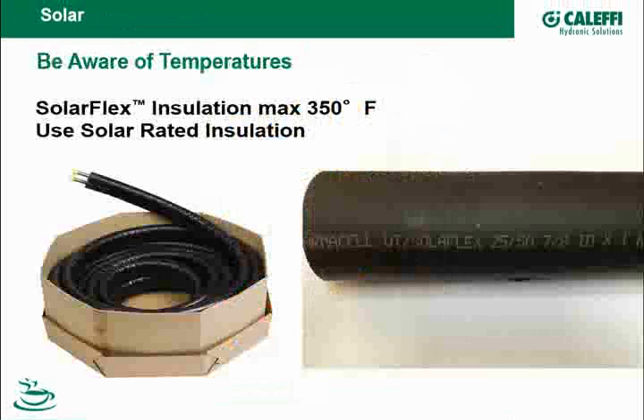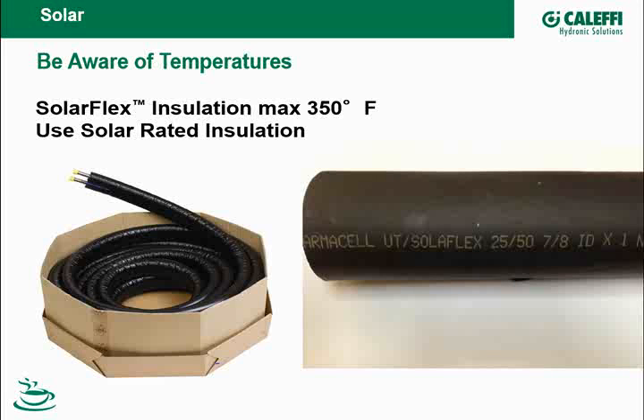Now, one thing to keep in mind is the temperature. If you start talking about solar applications, the stagnation temperature of a collector is well over 300 degrees, and evacuated tubes probably well over 400 degrees. So you've got to pay attention to that when you start insulating solar tubing, certainly the stuff close to the collector. The companies that make insulation, like here's an example of an Armacell brand, actually make a solar insulation now. A couple things about this: it's a little thicker wall, but also it's a higher temperature insulation to be able to withstand those temperatures. So probably a little bit more EPDM in here than other products to be able to do that.